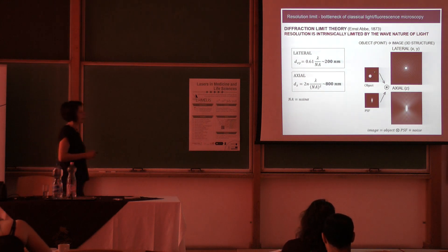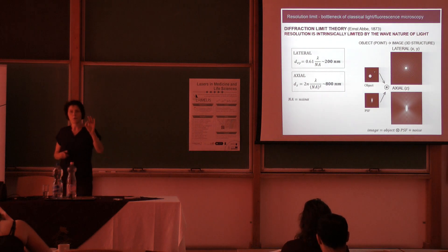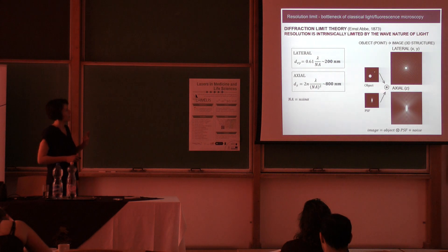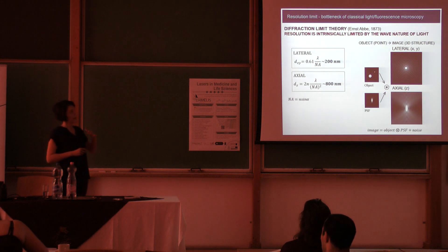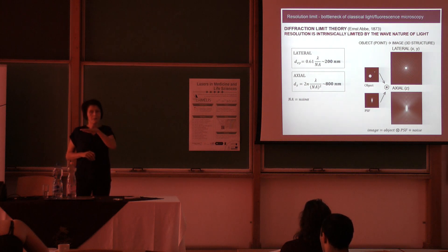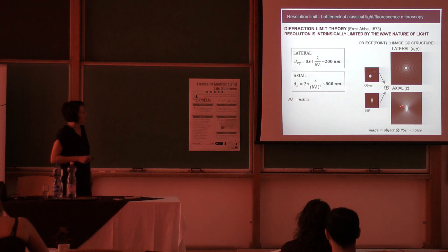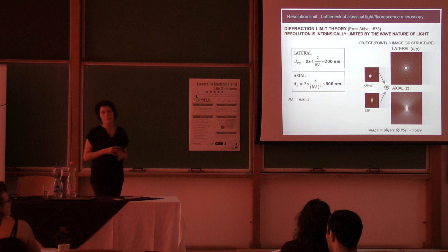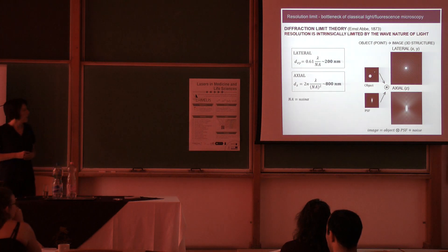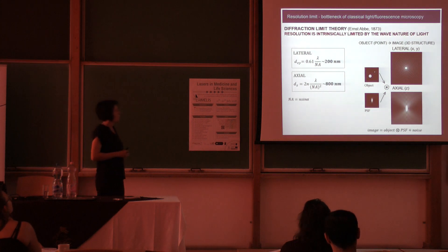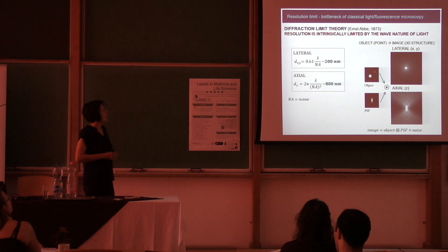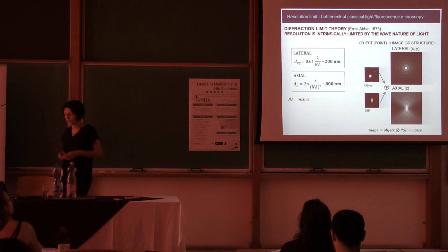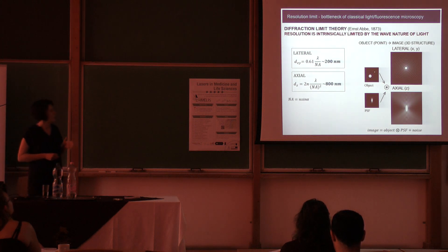...what you get is not a concise point on your image, but a three-dimensional interference pattern. It has different shapes in the lateral direction — the XY plane parallel to the coverslip — and also an elliptical shape in the axial direction (Z), which is perpendicular to the coverslip. Due to this phenomenon, the smallest things you can distinguish are separated by a few hundreds of nanometers. In the lateral direction it is approximately 200 nanometers at best, and in the axial direction the resolution is worse — approximately 800 nanometers.